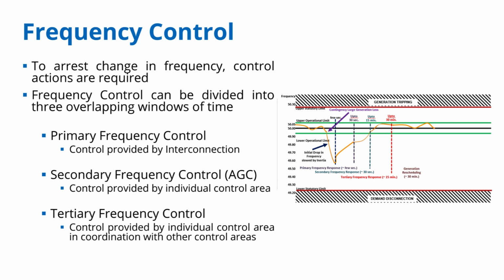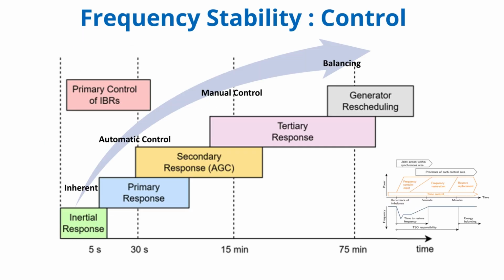And stopping those frequency changes requires control actions. The material describes three layers: primary, secondary (AGC), and tertiary. This is the standard hierarchy. Primary frequency control is the immediate automatic response. Happens within seconds. How does it work? It's usually built into generator governors, their speed controllers, and increasingly into inverter controls. They sense the frequency deviation locally and automatically adjust power output slightly to counteract the change. It's a proportional response, like droop control. Its job is to arrest the initial frequency swing, stop it from going too far too fast. Everyone contributes. Okay, stabilizes things initially, then secondary control, AGC, kicks in.